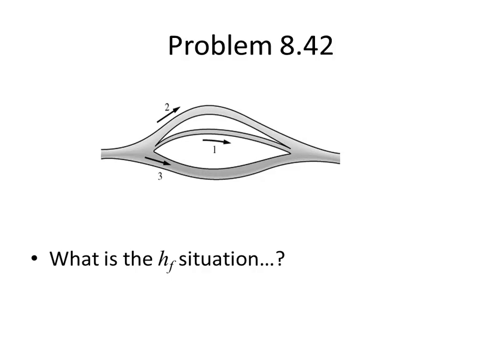And so just naturally, more of the water will go through the big pipe, and so the velocity will be higher, and it'll all just come into equilibrium so that what's equal through all those 3 different routes is how much energy it takes to get through it. So the beginning energy state as the junction appears, and when the pipes come back together at the exit junction, they all have experienced the same losses and end up with the same amount of head coming out of it.